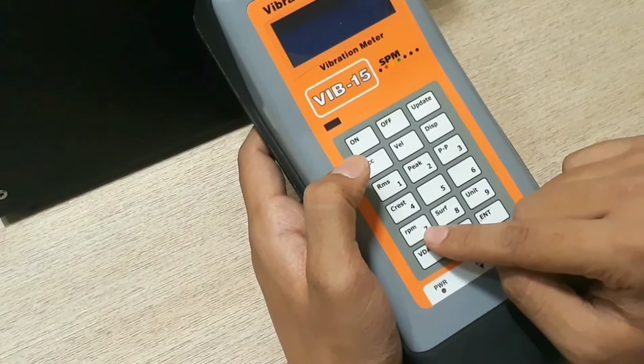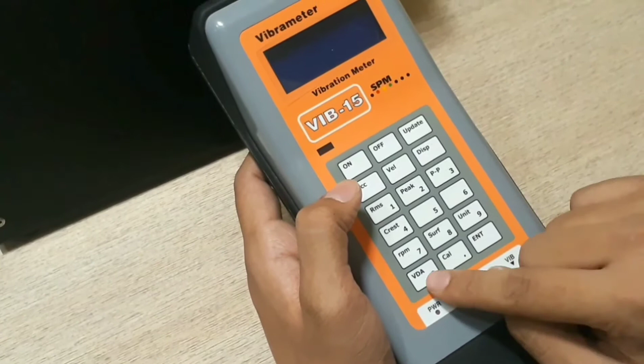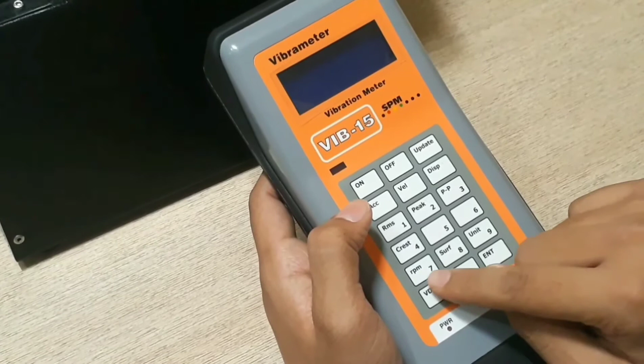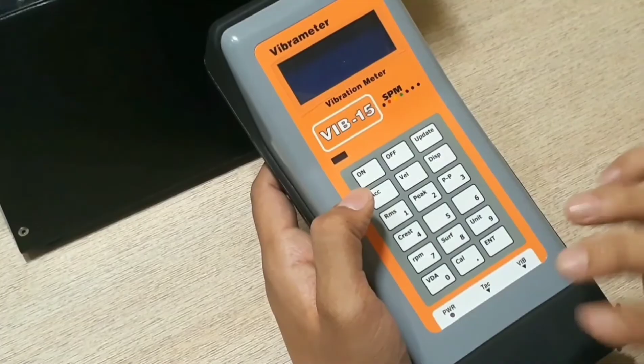Here, with the help of RPM, we can measure the RPM of a particular equipment. You can see here surf, which is nothing but surface speed, and VDA, which is nothing but velocity, displacement and acceleration. All the readings will be obtained simultaneously with this option. As you can see, this is our vibration transducer with a magnetic base.